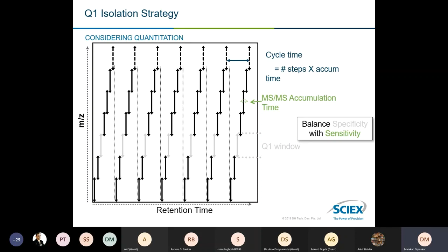So the cycle time depends upon the number of steps and the accumulation time. The accumulation time can be reduced down to 10 milliseconds, which is the highest speed the instrument can offer. The number of steps is the number of SWATH windows we consider, like say 100 windows with a 10 millisecond accumulation time can give a cycle time of around 1 second. So a 1 second cycle time, for UPLC scale analysis like a 10 second peak width, we are able to get a minimum of 10 data points across the peak. So that is the way we can do it.